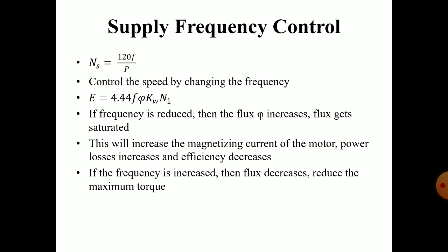Usually the induction motors are designed to operate at the knee point of the magnetization characteristics. So with the increase in the flux, the magnetizing current of the motor increases and the losses increase, which decreases the efficiency. Similarly, if the frequency is increased, then the flux decreases, which reduces the maximum torque capability of the machine.